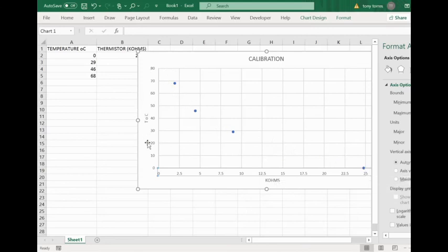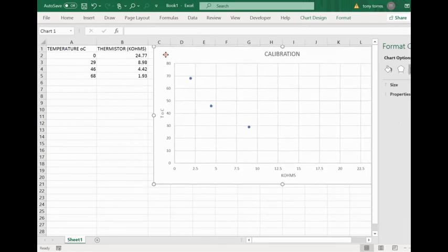Let's see, at 25 degrees, the reading will be somewhere here. I don't know. You see, between this point and this point, you will end up being somewhere here, a little bit higher than perhaps 12.5. It doesn't matter. What I'm saying is, the next time we talk about calibration, it's not going to be directly kilo ohms. It will be voltage. I'm only checking how good my sensor is, how well it works.